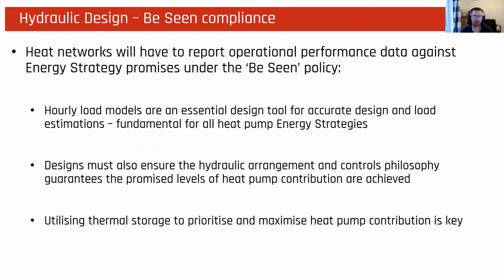In terms of the hydraulic design of thermal storage, I just wanted to flag the compliance requirements, particularly in the London Plan that's coming through. Promises that are made at energy strategy stage are going to have to be delivered against, and we will have to report operational performance data and prove that we're delivering against those energy strategy commitments. For this, we need hourly load models to make sure that the design tools we're using are accurate, and we're getting really good, accurate load estimations to size our heat pumps and thermal storage to meet those promises.